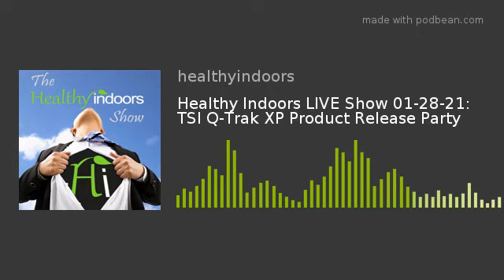Excuse me, but the ventilation tools are capture hoods for doing direct airflow measurements from your supply and diffusers. That's one of the number one tools of a test and balance guy. They go off the specs. This room is designed for 1,280 cubic feet per minute at a certain amount of air changes per hour.